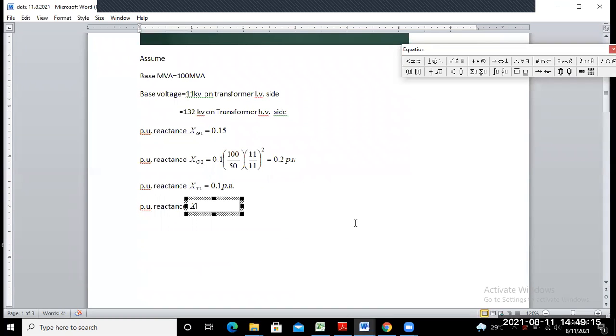X T2, per unit old value is how much? 0.8. 0.08, na. 0.08. What is the per unit MVA new value here? MVA new value कितना होगा? 100. कॉमन हम लोग क्या चूज कर रहे हैं? 100 base MVA. That means new MVA is your 100 MVA and new base voltage is your 11 kilovolt.